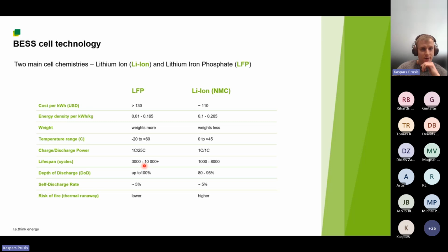which is also a very important factor if we talk about grid stabilization, grid balancing applications. Also, LFP batteries have a longer lifespan, which is measured in cycles, and one cycle is a full charge or discharge, with a note, of course, that it must be properly charged or discharged, and we're going to talk about it in the following slides. Also, a good feature of LFP batteries is that you can discharge them up to 100%, while lithium-ion you can discharge from 80 to 95%.